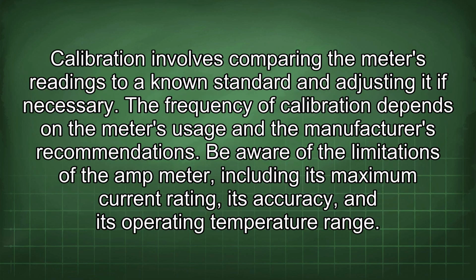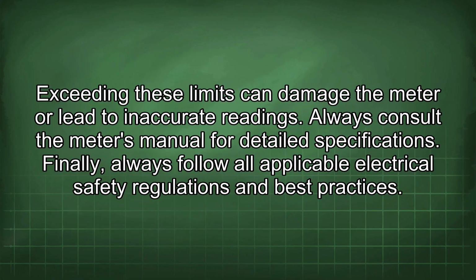Calibration involves comparing the meter's readings to a known standard and adjusting it if necessary. The frequency of calibration depends on the meter's usage and the manufacturer's recommendations. Be aware of the limitations of the ammeter, including its maximum current rating, its accuracy, and its operating temperature range. Exceeding these limits can damage the meter or lead to inaccurate readings. Always consult the meter's manual for detailed specifications.